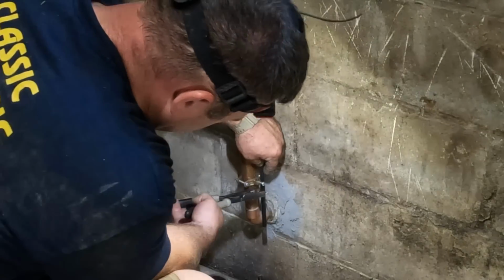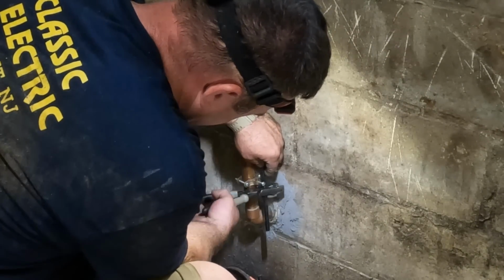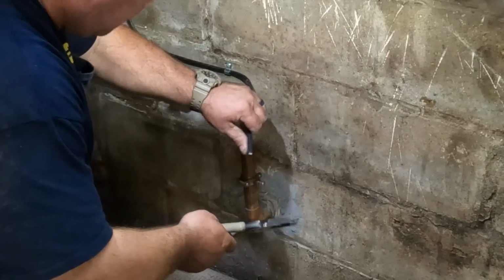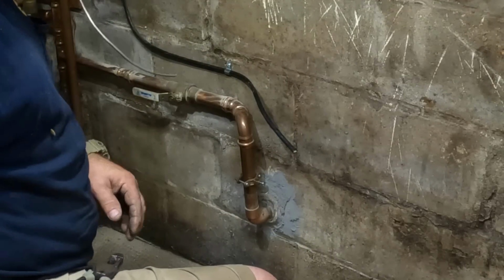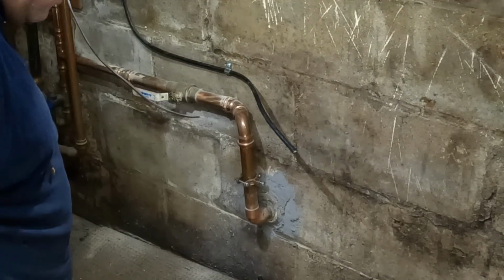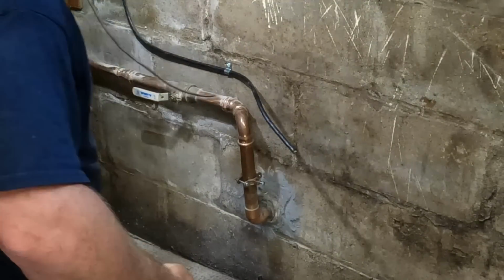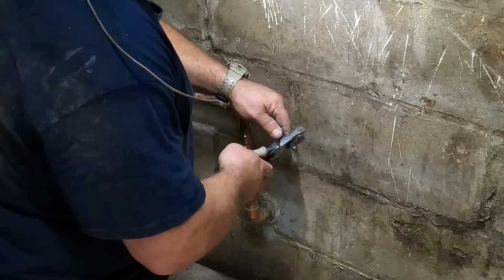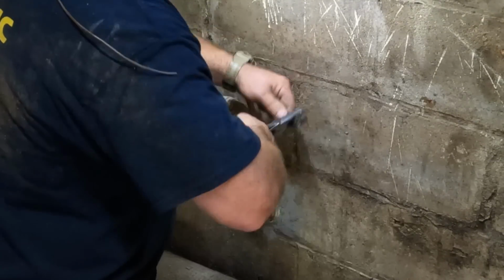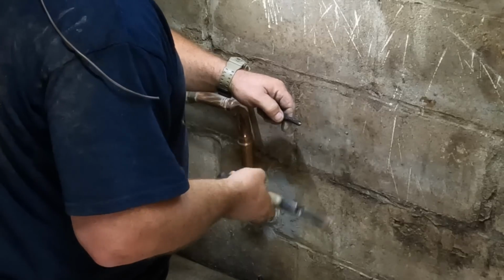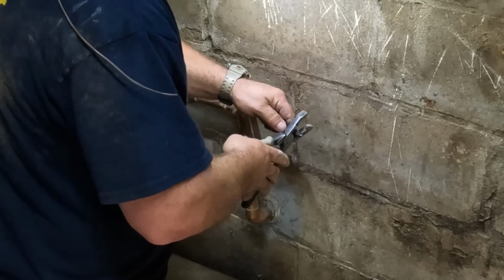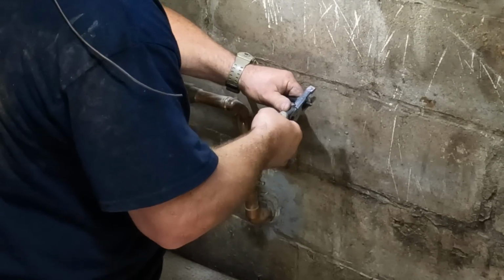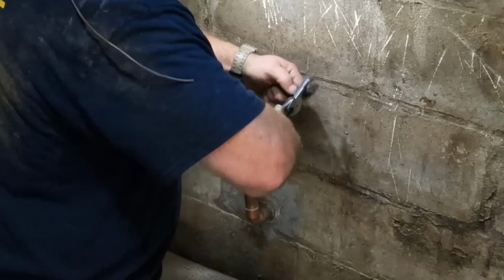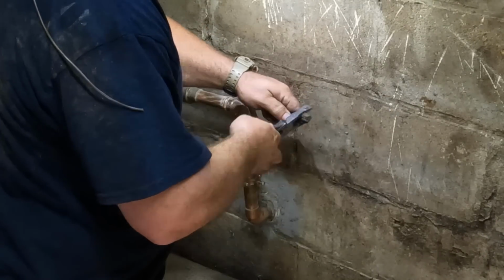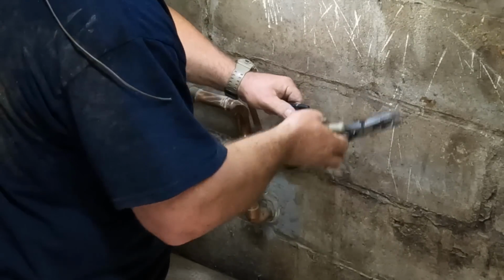Here I'm using a brass water ground clamp, and usually I use some emery paper to clean up the copper so I get a nice connection to the copper itself. Remember, you want to bond the water pipe so you limit the potential for current to flow on it. So you want to make sure you get a good bond. That's why you use the emery paper. But this copper was so new that I didn't feel the need to do that.